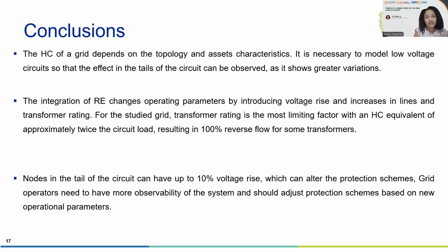Well, in this work, we made a hosting capacity method that integrates Monte Carlo simulation with DIgSILENT PowerFactory and Python to be able to evaluate the hosting capacity. It depends on the topology of the grid and also on the asset characteristics. And there is a need to model low voltage circuits so the impact of the integration of renewable energy can be evaluated. In this case, the tails of the circuit are the most affected by voltage rise. Also, the integration of renewable energy changes the parameters of the grid, introducing voltage rise and changes in the rating of the feeders and transformers.